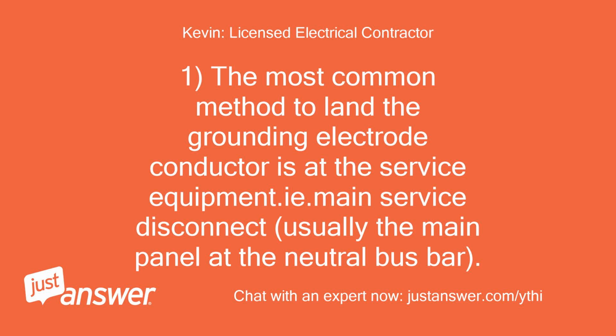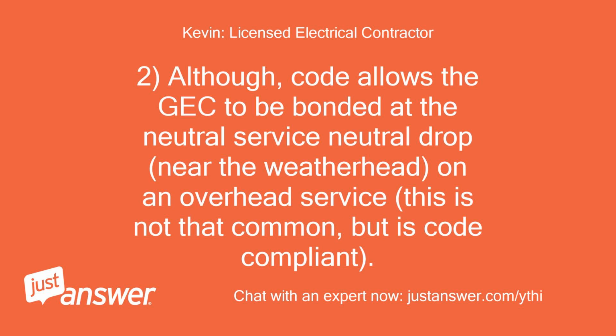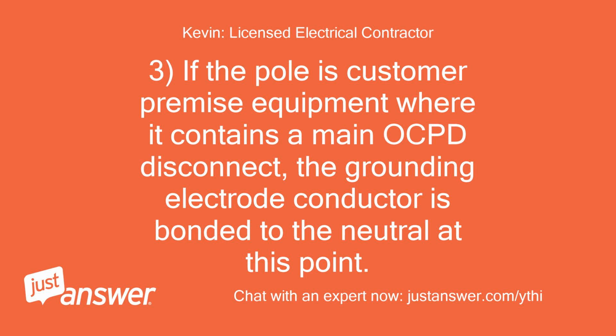1. The most common method to land the grounding electrode conductor is at the service equipment, i.e. the main service disconnect, usually the main panel at the neutral bus bar. 2. Although code allows the GEC to be bonded at the service neutral drop, near the weatherhead, on an overhead service, this is not that common, but is code compliant. 3. If the pole is customer premise equipment where it contains a main OCPD disconnect, the grounding electrode conductor is bonded to the neutral at this point.